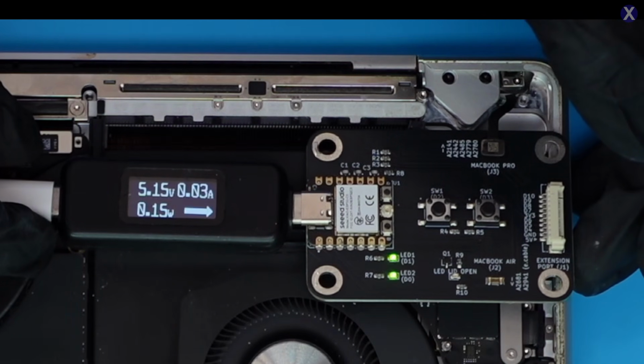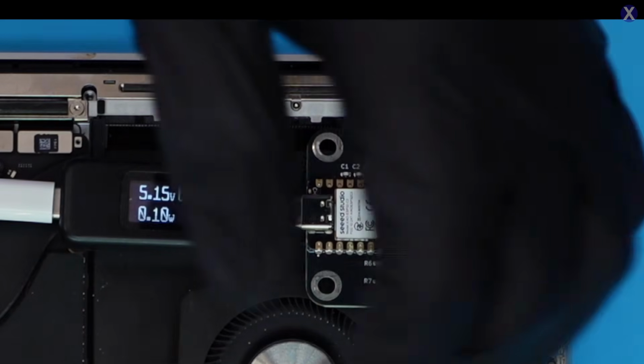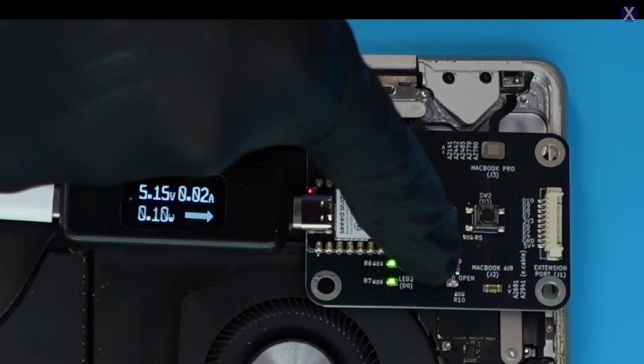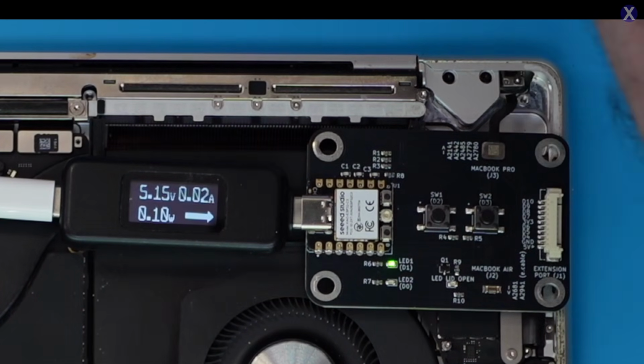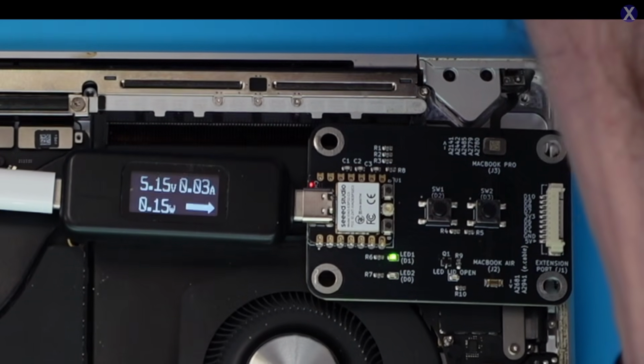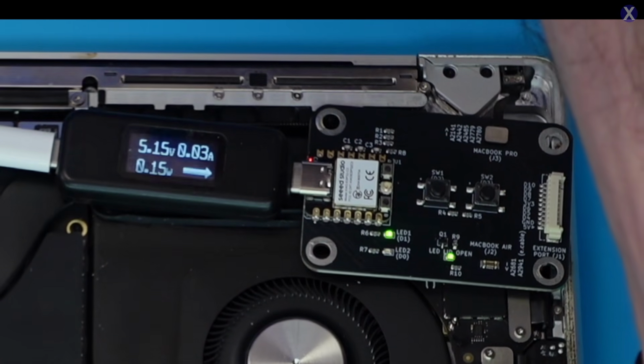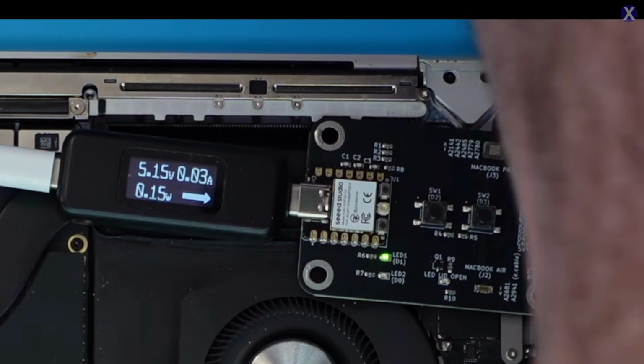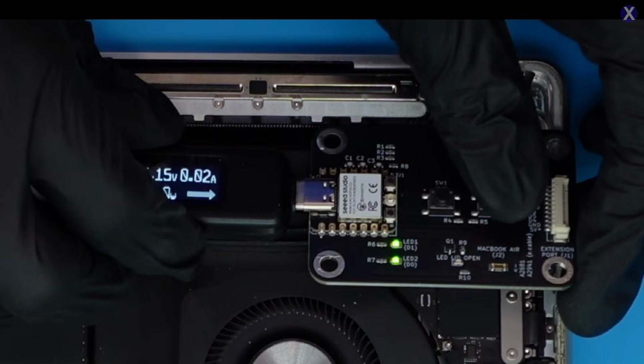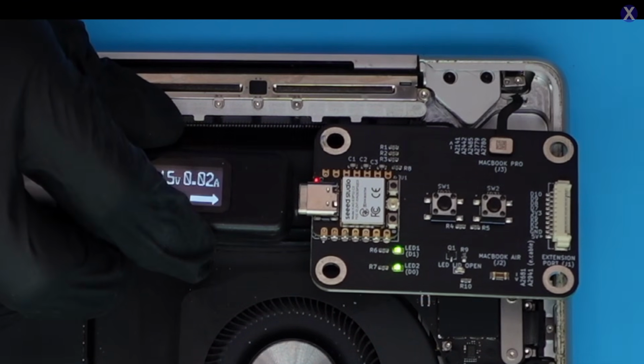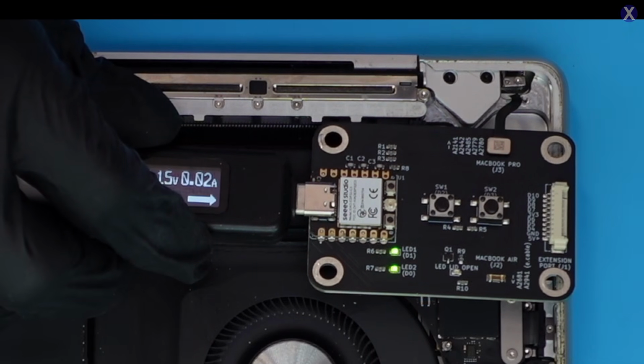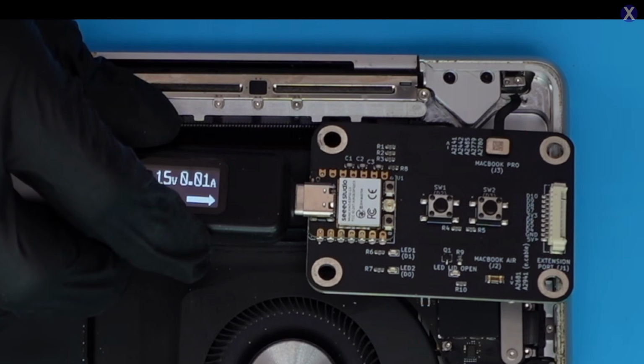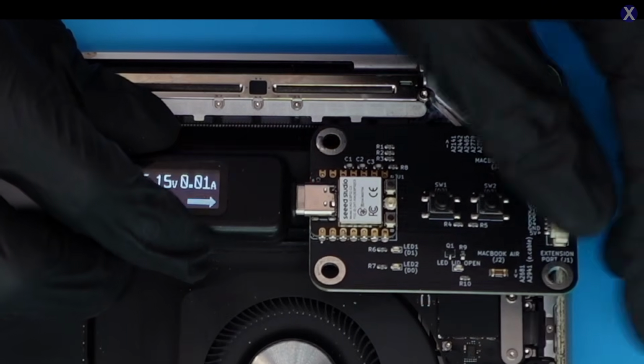We can test that right now to see. So we're going to open it up, and we'll see if the LED for lid opens when we open the device slightly, and it does. And then when we close it, it goes back off. So that looks to be pretty good. Now I'm going to save it. So it's going to save directly there, and then that's it. After that, there's no going back. Okay, so everything went off, so everything's been calibrated properly. So we can go ahead and unplug it now.